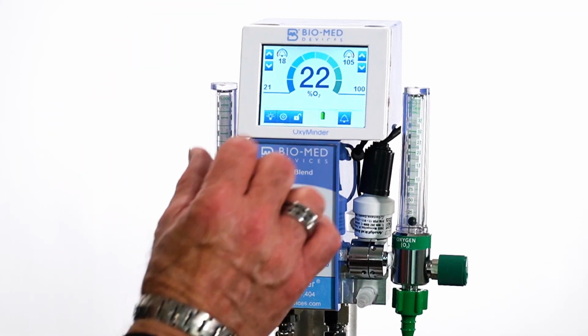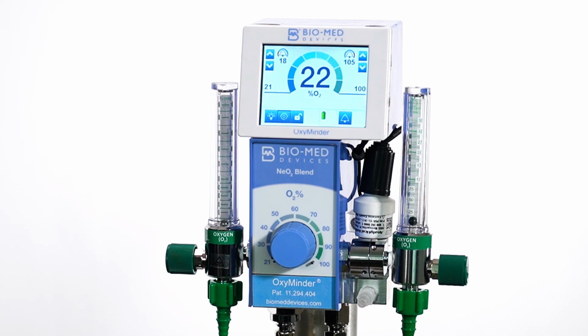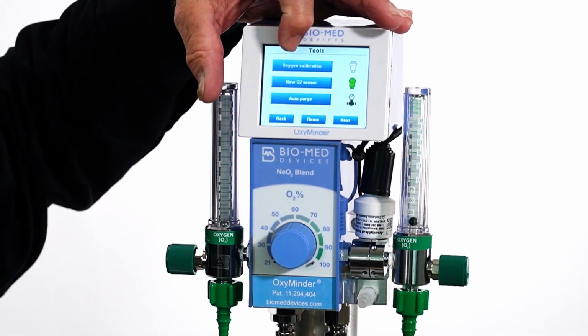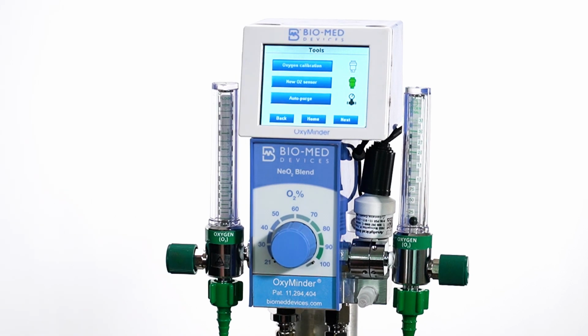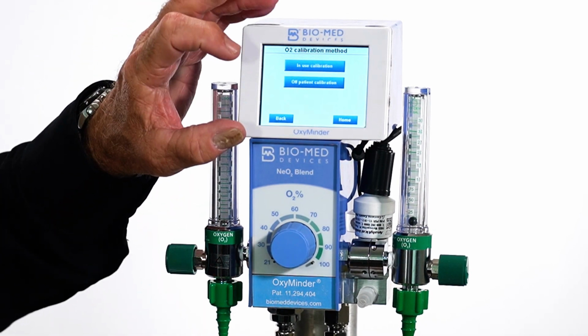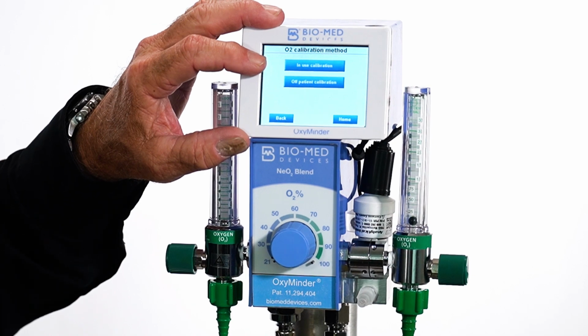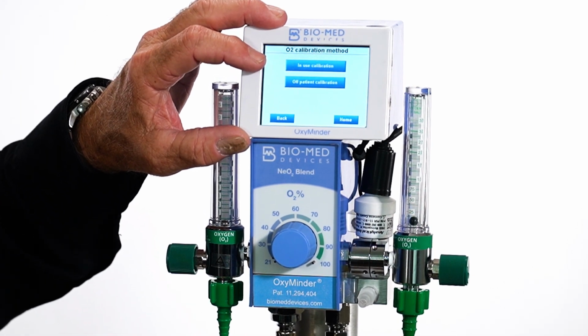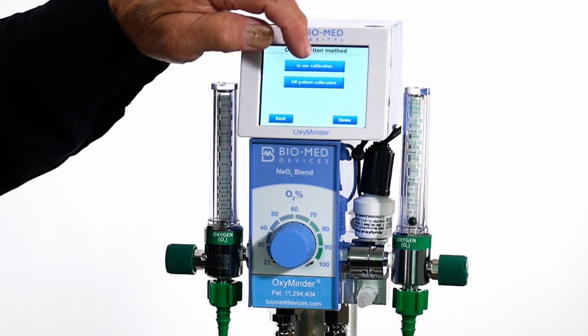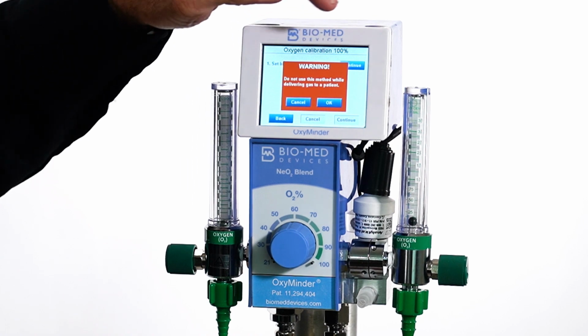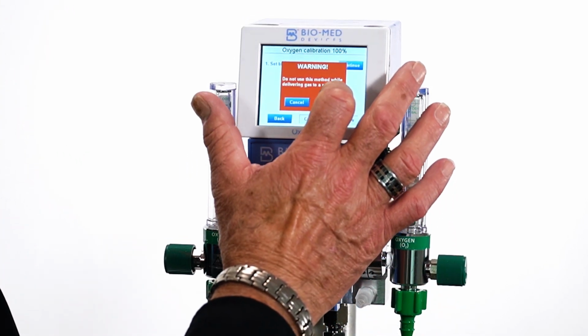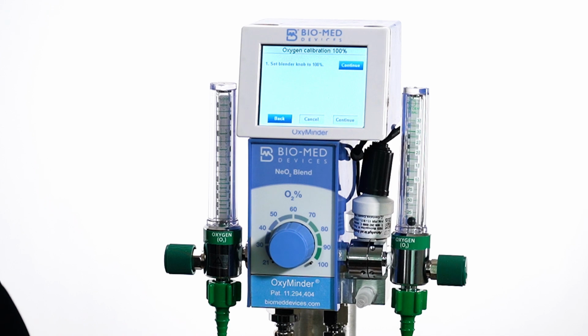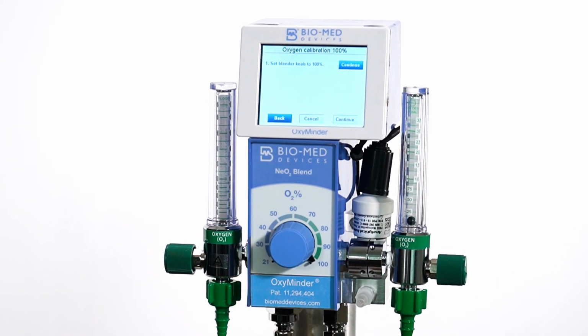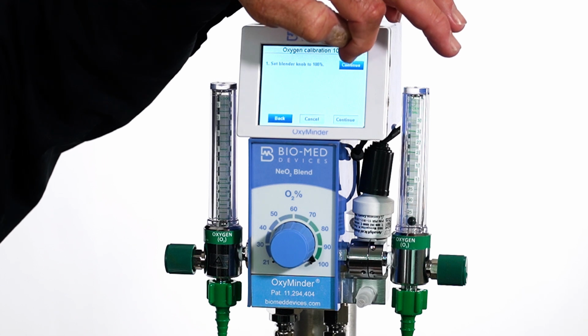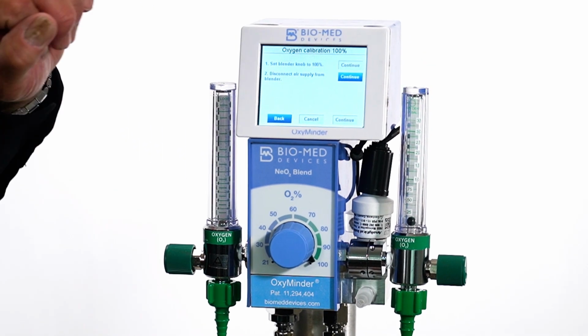As far as the screens, if I hit that gear, you can do your oxygen calibration, and we'll go ahead and do this. We can actually calibrate this while it's on a patient if we need to. What I'll do now is do off patient calibration. It says do not use this method while you're on a patient.